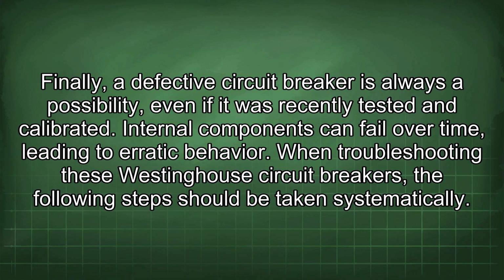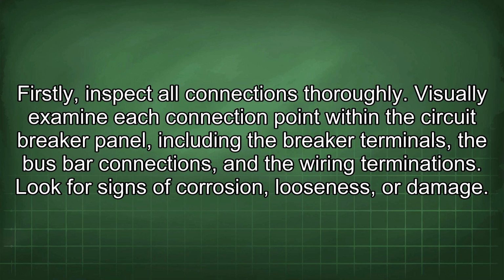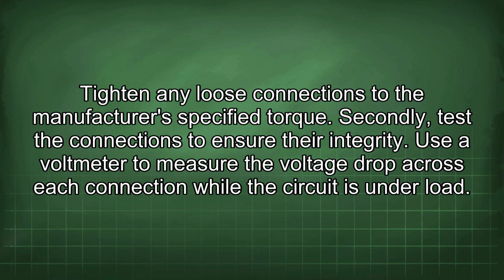When troubleshooting these Westinghouse circuit breakers, the following steps should be taken systematically. Firstly, inspect all connections thoroughly. Visually examine each connection point within the circuit breaker panel, including the breaker terminals, the bus bar connections, and the wiring terminations. Look for signs of corrosion, looseness, or damage. Tighten any loose connections to the manufacturer's specified torque.